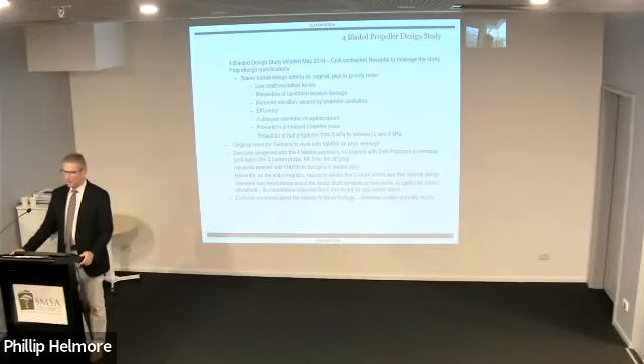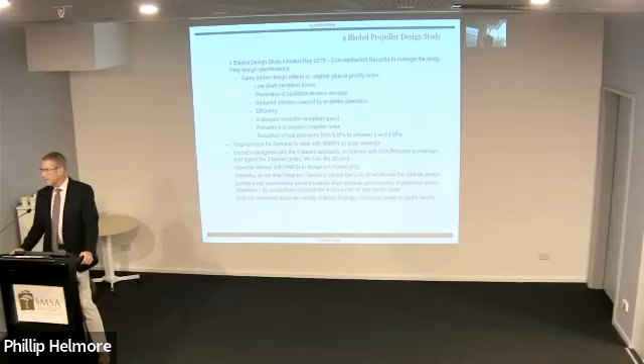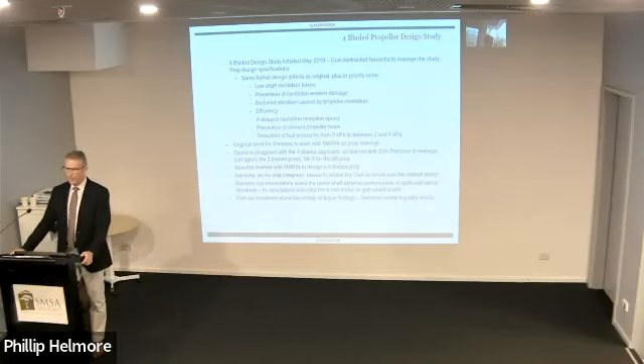At the same time, Siemens had reservations about the motor shaft dynamic performance, particularly the lateral vibrations. They did some calculations which showed the 6mm air gap in the motor would close with a 4-bladed propeller. We were not happy about this - in fact we didn't really believe it. So we asked Siemens to justify their results, and they couldn't.